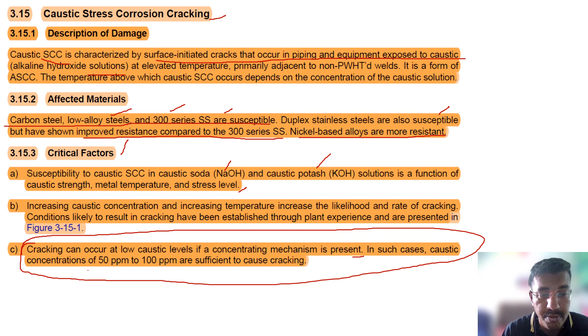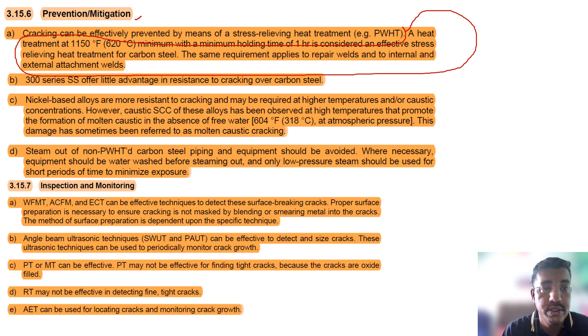So how to prevent it? A heat treatment is required. For caustic stress corrosion cracking avoidance, we have to do a heat treatment, okay, PWHT, 620° minimum with a minimum holding time of 1 hour is considered an effective stress relieving heat treatment for carbon steels. 300 series SS offer little advantage in resistance to cracking over carbon steels. Nickel-based alloys are most resistant to cracking and may be required for high temperature and caustic concentration. However, caustic stress corrosion cracking of these alloys has been observed at high temperatures that promote the formation of molten caustic in the absence of free water.